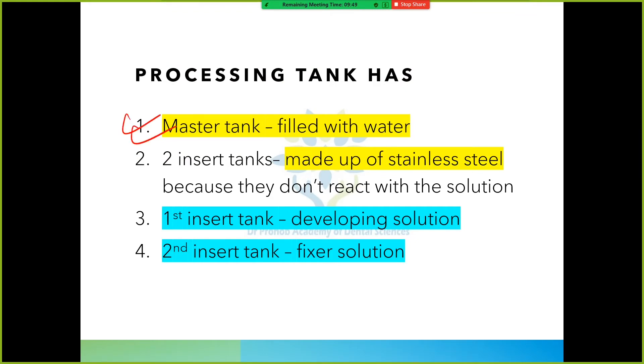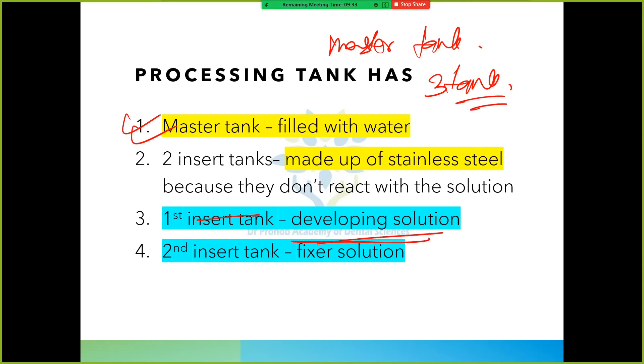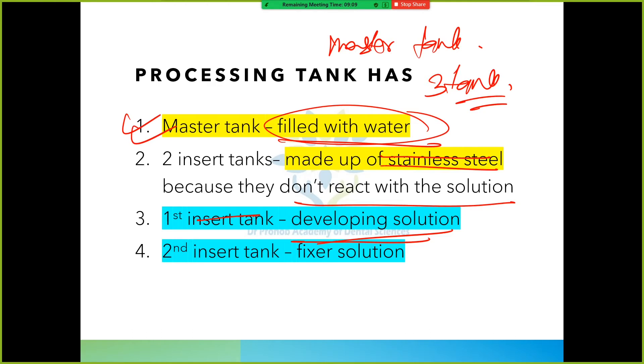In the processing tank, there is one master tank filled with water, made up of stainless steel - because stainless steel does not react with the solution. The developer or fixer doesn't react with stainless steel. Inside, there are two insert tanks: the first insert tank contains the developing solution, and the second insert tank contains the fixer solution.